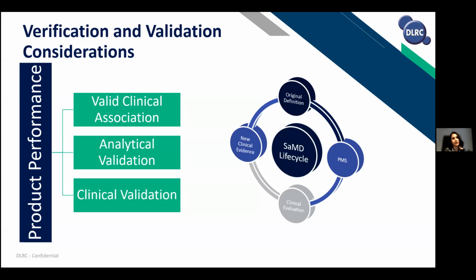Next slide, please. So once you've decided your device classification, then you need to start to determine how you're going to show product performance. The first thing to look at is the valid clinical association. And this is where you need to determine whether the outputs of your software, based on your inputs and the algorithms on which your device is based, are providing information for your targeted clinical condition. In our case study, we would need to provide evidence that the condition of interest causes those specific abnormalities that are being localized in the images and tagged in the images. So this can be demonstrated by scientific literature, clinical research, or professional guidelines.